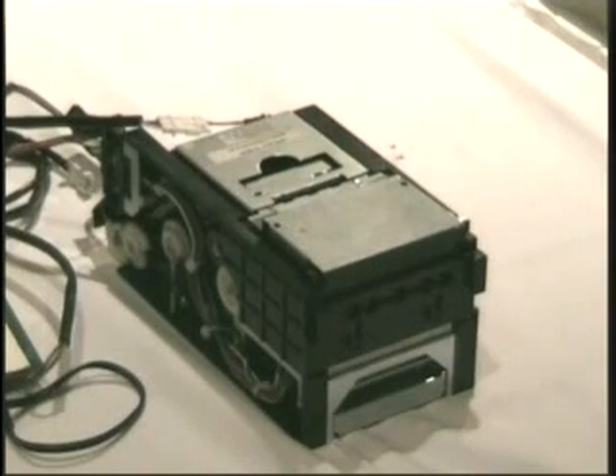The only problem you're going to have with the calibration paper, number one, never try and handle the white part with your fingers because you've got oils in your skin and stuff. It'll get on there. Make sure you don't have dirty hands ever when you're cleaning it, coin dust and stuff like that. As long as you keep the white part of the paper clean, and you cannot clean it. I had one guy say, oh yeah, whenever that gets dirty, we just take a little alcohol, clean it off. Problem is you're also taking that coating that we put on it off.